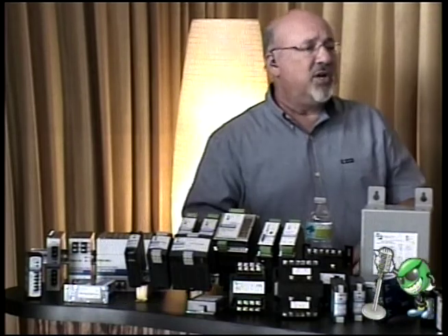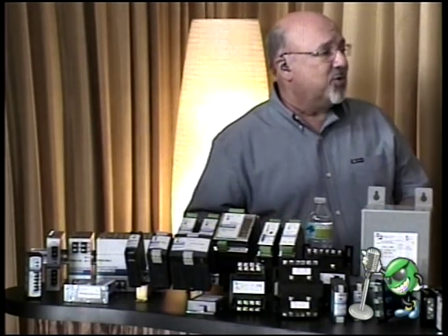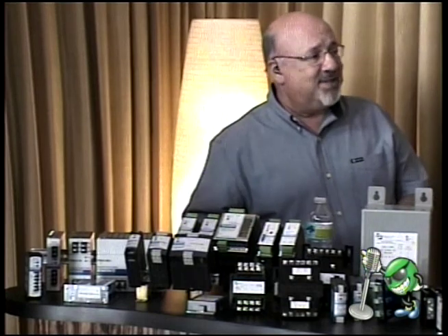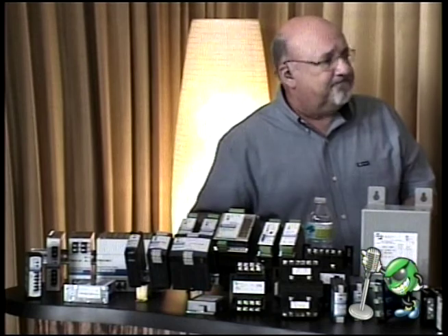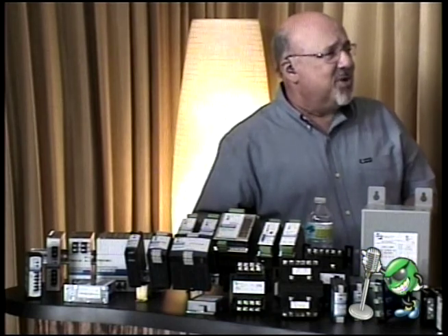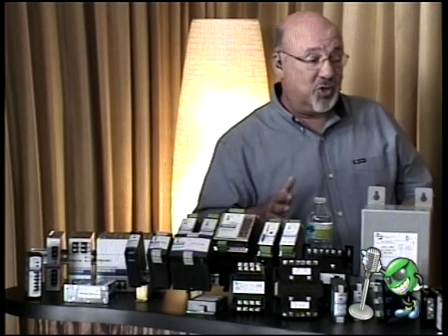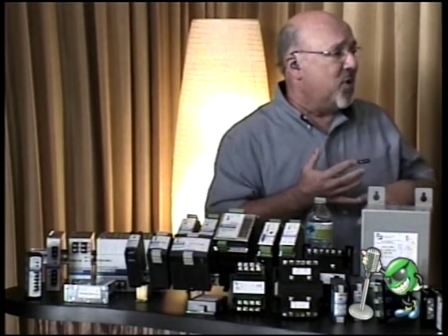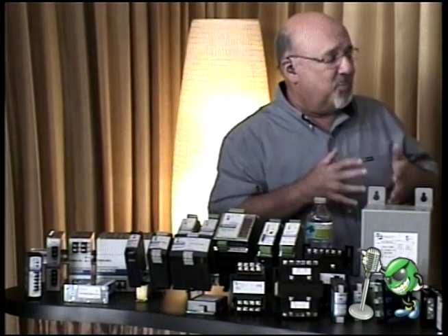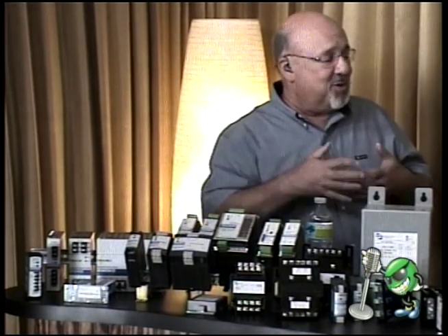If all we have is a bunch of solenoid valves, and we need 24 volts going to them through a DC output from a PLC output module, solenoid valves are going to create a lot of harsh environment stuff anyway. That's going to be one of our webinars in the future, to talk about noise suppression. But you're not necessarily going to need precise regulation, so you're going to be able to afford most DC power supplies.